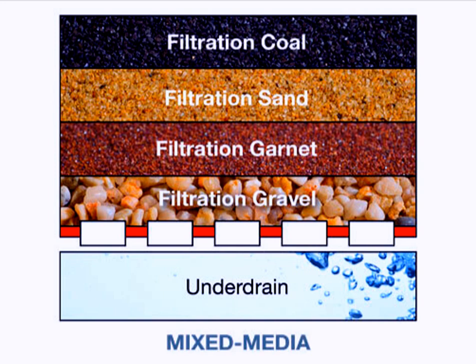Filter sand. The sand used for filtration is specifically manufactured for filtration use. If the sand is too fine, it will resist the flow of water and require frequent backwashing. If the sand is too coarse, it may not effectively remove turbidity.